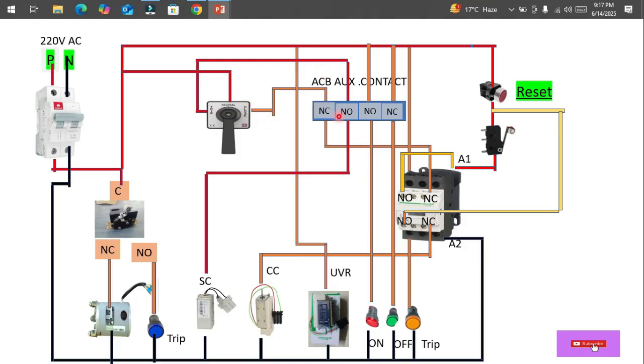With no fault present, power flows through the NC contact and then reaches the next NC contact — which is NC when there is no fault. It then travels to the closing coil. Once the closing coil receives power supply, it closes the ACB by pushing the plunger, making the circuit.